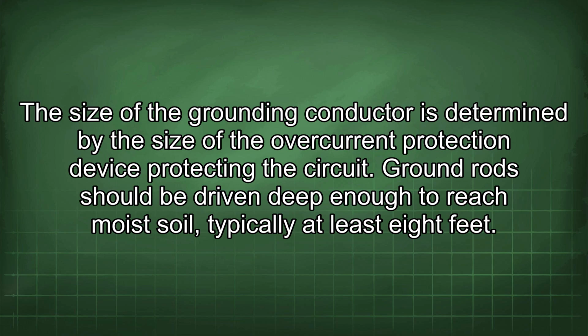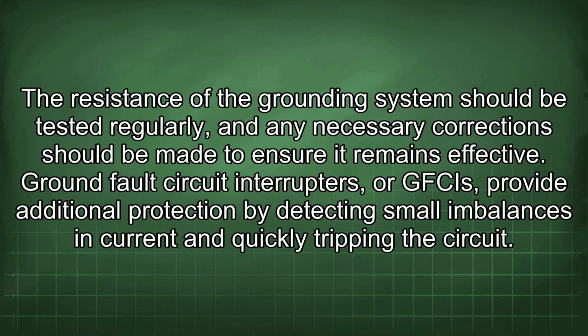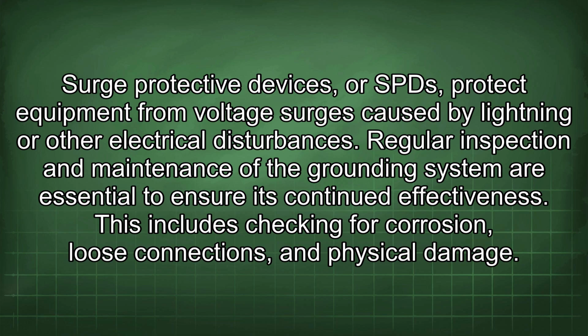Ground rods should be driven deep enough to reach moist soil, typically at least 8 feet. The resistance of the grounding system should be tested regularly, and any necessary corrections should be made to ensure it remains effective. Ground fault circuit interrupters, or GFCIs, provide additional protection by detecting small imbalances in current and quickly tripping the circuit. Surge protective devices, or SPDs, protect equipment from voltage surges caused by lightning or other electrical disturbances.